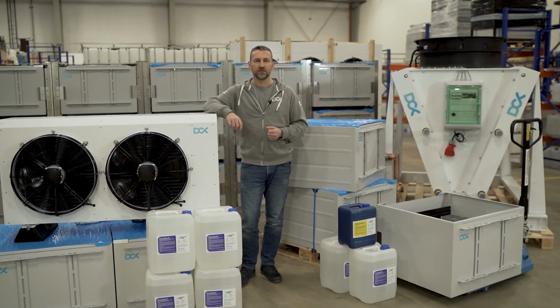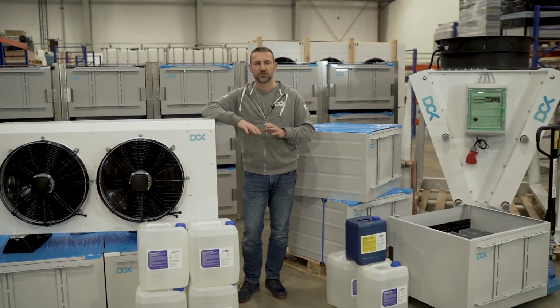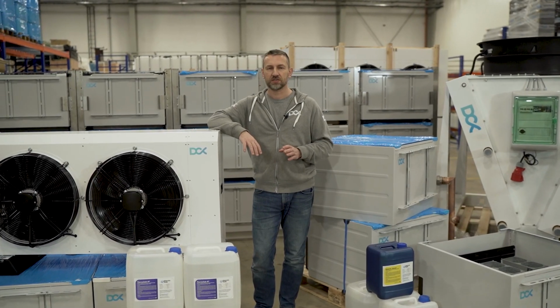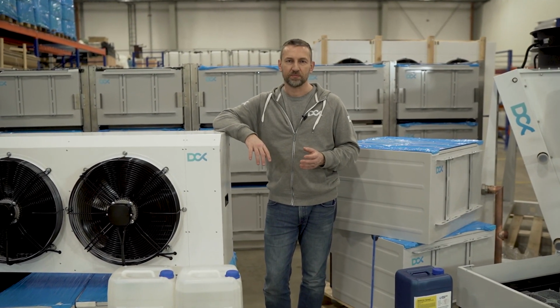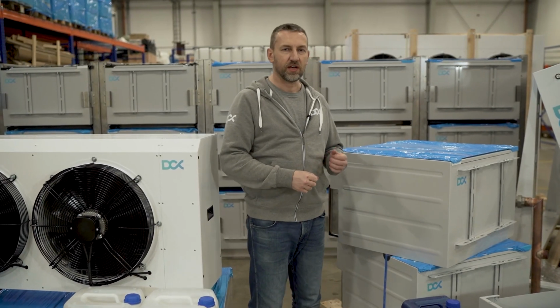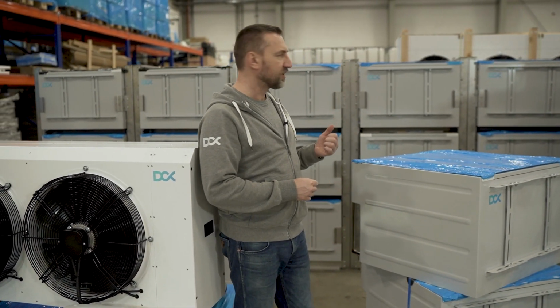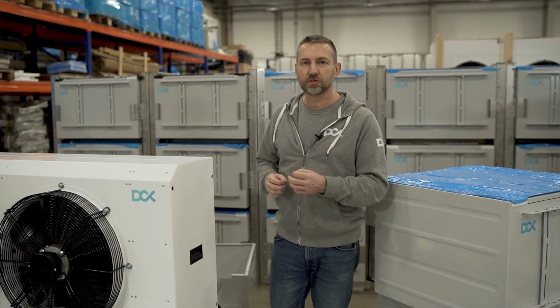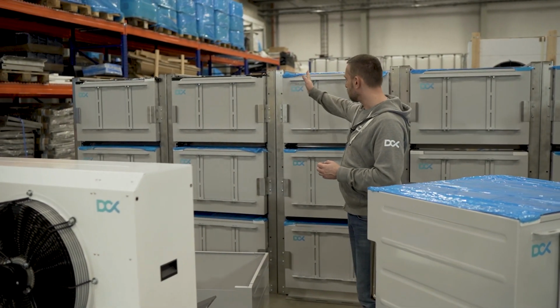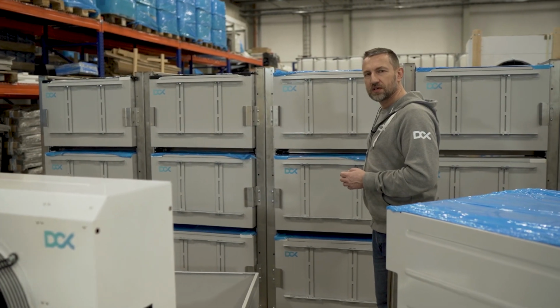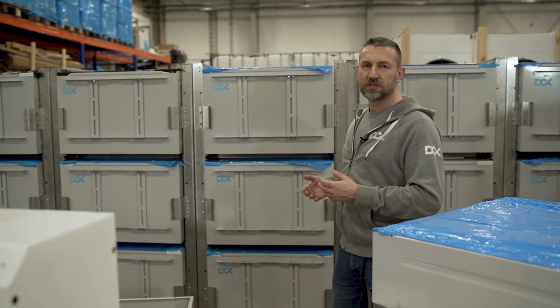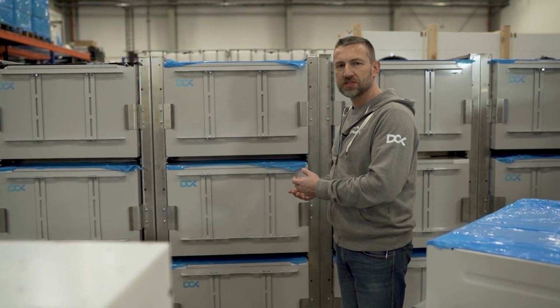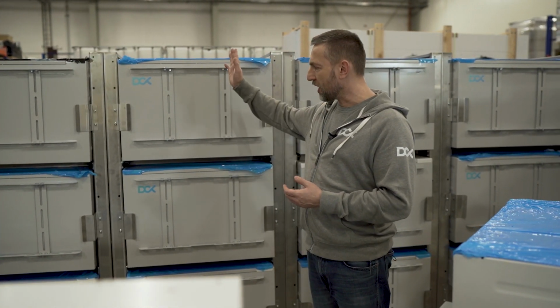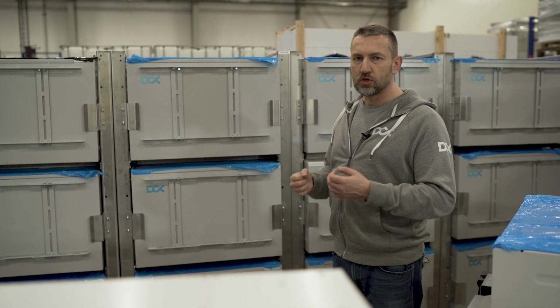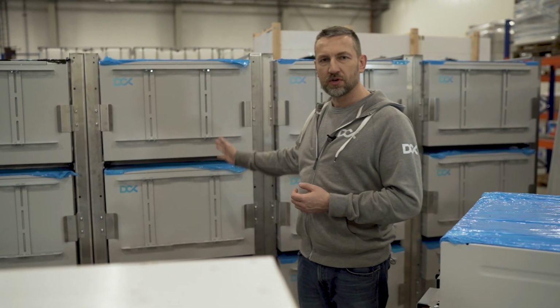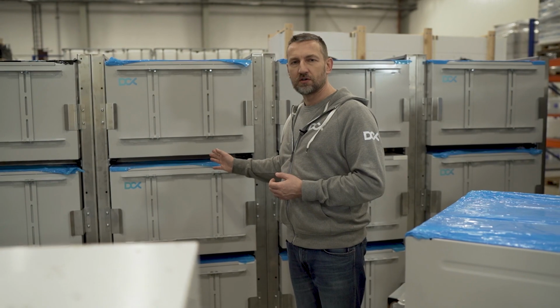In our case, the immersion mining system we provide is extremely dense — there's no other solution like it, because we use a typical rack system. The rack system, which you can see behind me, allows mining in 1 square meter of space. You can put 120 to 140 kilowatts of power here. 140 kilowatts means a huge amount of miners — 24 S19 miners, or 36 of the M10 family.